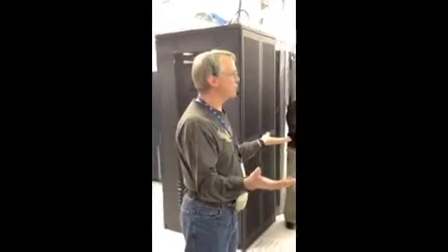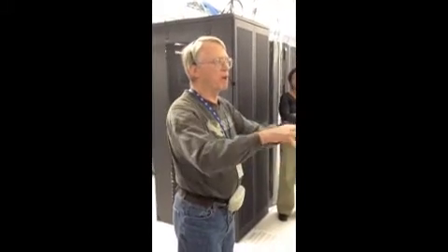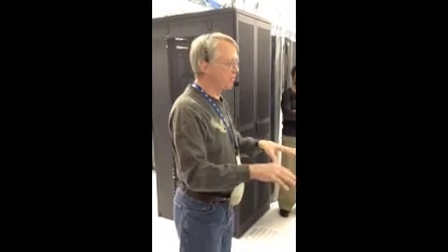So what we ended up doing is using water-side economizers, basically giant evaporative coolers. And those work because of the dry air here. They work extremely well. So it turned out the most valuable asset that Colorado has is not its cold air, but its dry air. And then we have that backed up with chillers. We're going to visit all of this stuff today as we go through. And so the chillers alone can supply all the cooling needs for the data center if it turns out to be very hot and humid, so that the evaporative coolers don't work well.